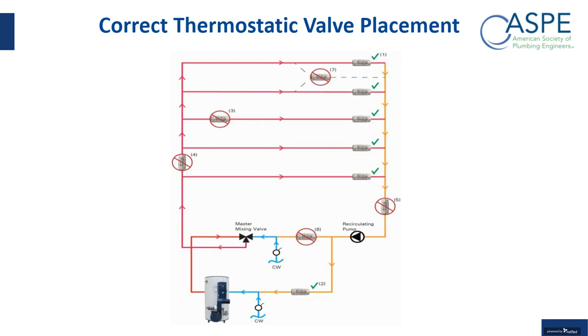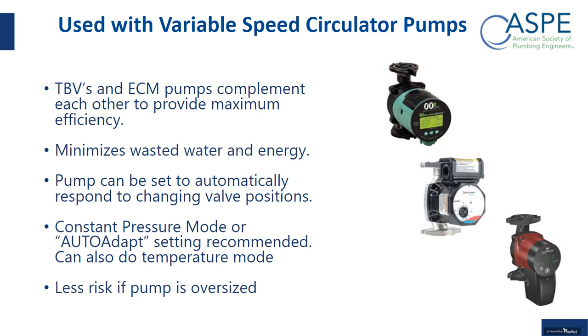But like for instance, here where I have this red circle and a line through it, I've seen cases where people would put a manual balancing valve at the output of a pump for the reason that they have that ability. If they needed to throttle down the flow of the pump because they felt maybe the pump was too large or something like that, they could just put a manual balancing valve there, leave it wide open, and then if they needed to throttle it down, they have the ability to do that. And then I've seen them in other locations in a recirc system for various reasons.